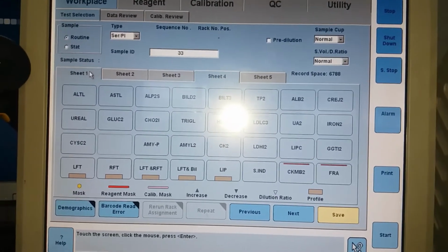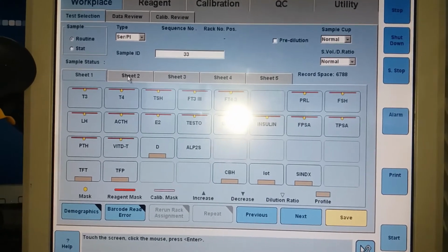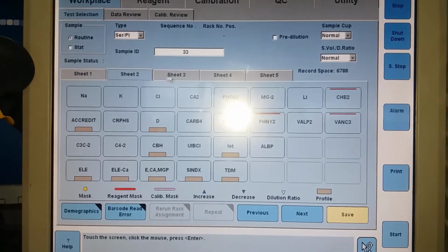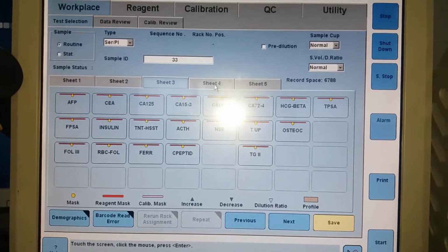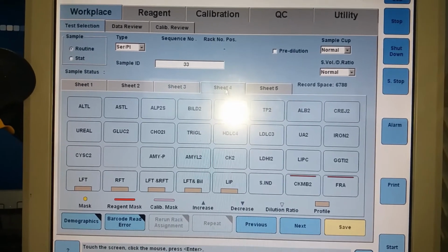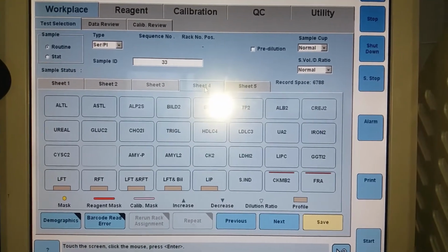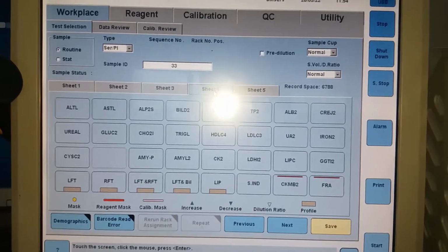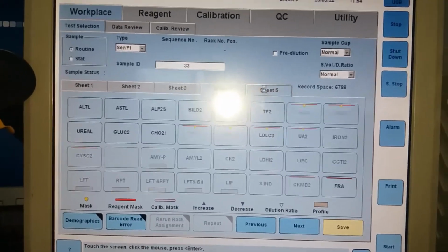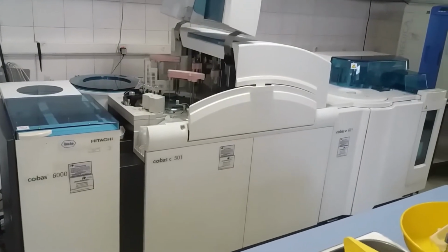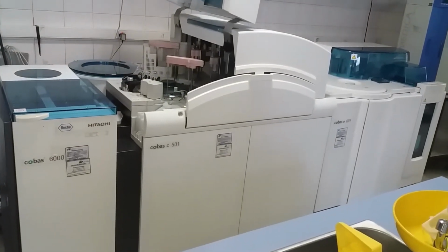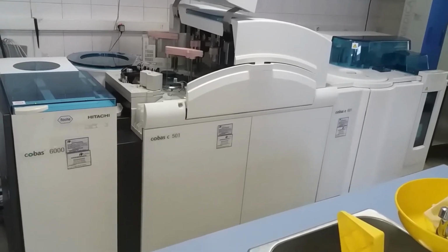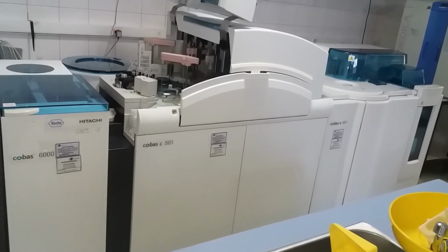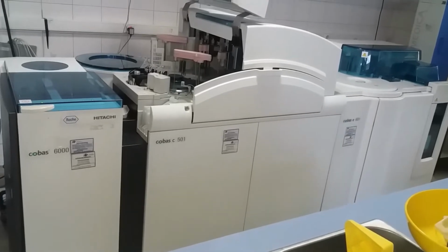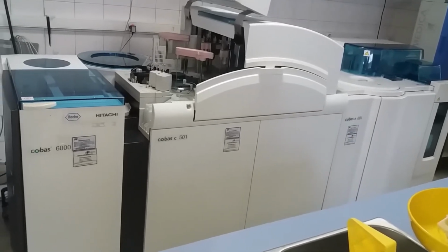When you see about reagents, up to 60 reagent cassette positions are available. There is an automated cassette management system, that is from registration, internal transportation, placement, and disposal. An automatic reagent cassette loading and unloading mechanism is also available. This machine has a sample database. It can store up to 10,000 data.